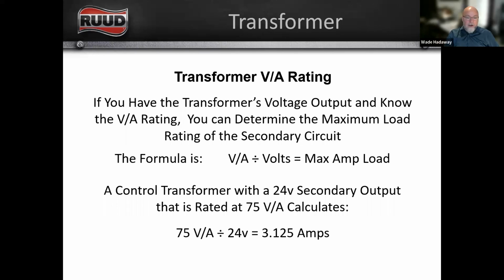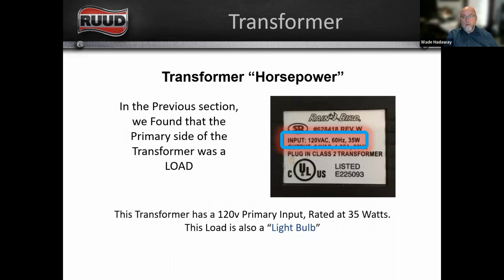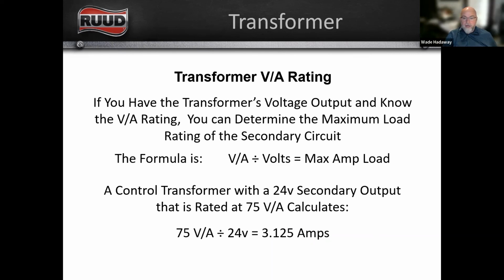So in this example, I've got a 75 VA transformer and a 24 volt secondary. Now, does every 24 volt system read 24 volts on your meter? No, but we're going to look at what our ratings are, right? So this output is rated at 24 volts AC, 30 VA, 1.25 amp, and that's where this calculation comes from. 75 VA divided by 24 volts: a 75 VA transformer rated for 24 volts can handle 3.125 amps.